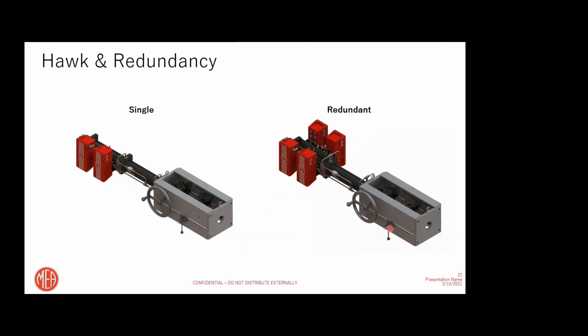But additionally, you can have completely redundant units with completely separate controls for two units. You'll have two separate sets of controls running one cylinder, and they will be fully redundant and independent. Another beauty of these units is that all of these boxes are the same, so they are interchangeable. You can put one on the other and it won't matter. With this type of setup, we get full redundancy, and you can get it for not that much cost. So now I will show you a Hawk interface, so you can get more familiar with how it looks and how easy it is to operate.